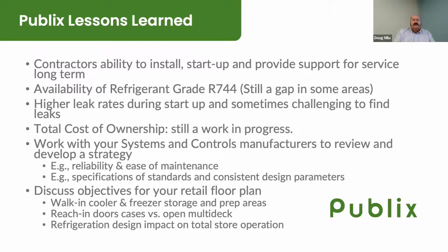So what you'll learn with CO2 is that it really likes to be in operation - it really doesn't like to sit idle in a vessel. So there are relief valves that, if the pressure gets too high, will safely relieve some of that pressure outside the machine center. That's what I meant by higher leak rates during startup.